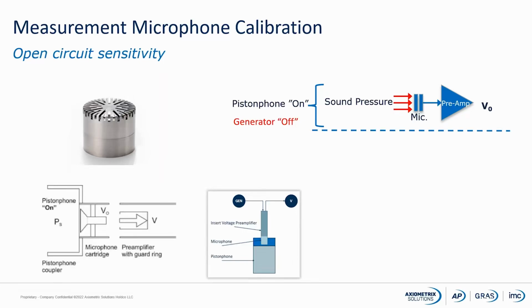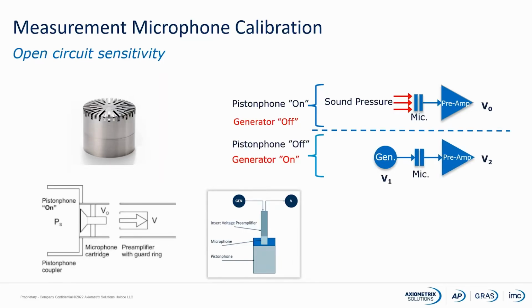Next step, we will switch off our piston phone, and then via our insert voltage preamplifier we will have a generator signal with a certain level. This generator will have exactly the same frequency as the piston phone, 250 Hertz. And then we will start adjusting the level of our generator. So we will adjust the level of the generator until we, on the output of the preamplifier V2, measure exactly the same as we measured before when we had the piston phone on.